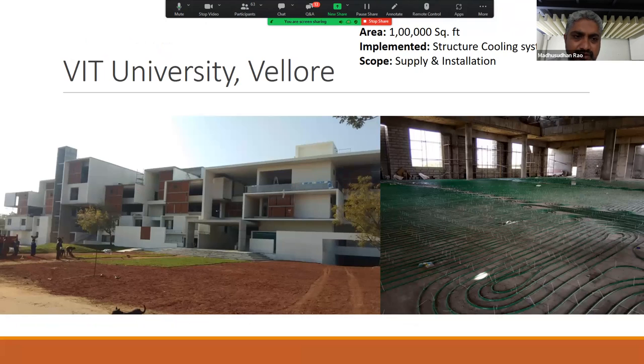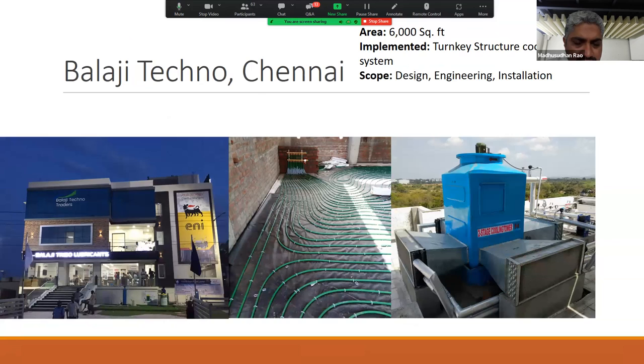Similarly, this is the architecture college at VIT in Vellore in Tamil Nadu, where it's run with a cooling tower. In this case, there is a small commercial building in Chennai where they hybridized it. This is 6,000 square feet. Normally, one would put about 40 tons of split AC in this building. So only 13 tons of split AC was put, along with structure cooling, and that split AC is used only when it is needed.